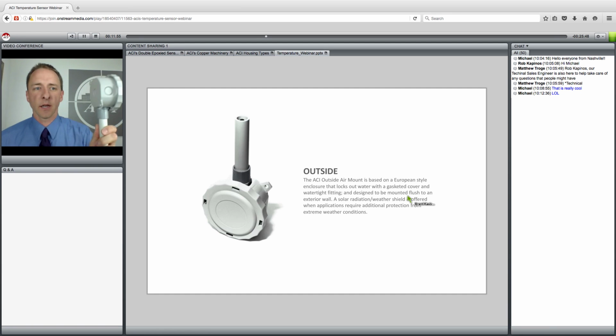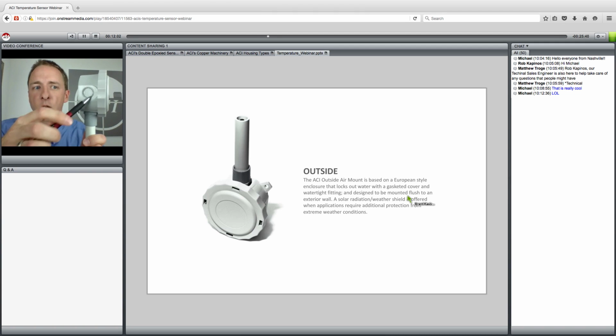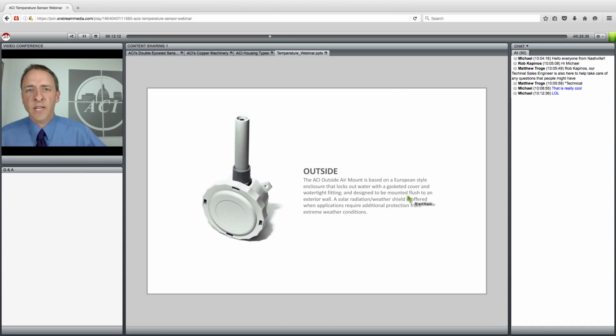One application note when installing this sensor: if you look closely, you can see there are 2 rings for the knockouts, an inner ring and an outer ring. We include a watertight fitting with this enclosure that fits the inner ring. Occasionally over the years we've had people send sensors back saying the sensor leaks and isn't watertight, and it turns out they had knocked out the outer ring instead. That outer ring is larger and fits a 1/2-inch conduit, but the watertight fitting we include fits the inner ring.